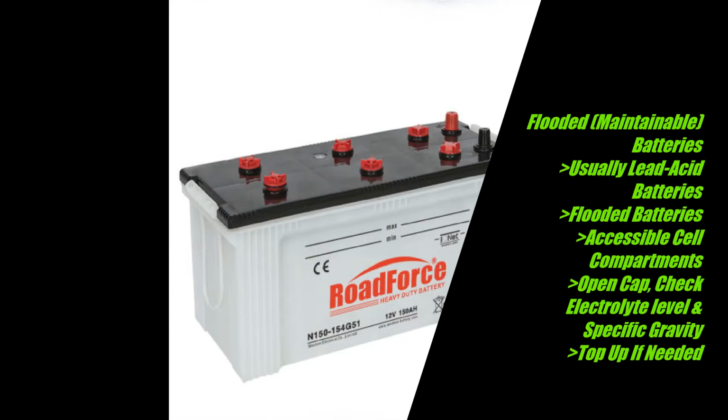So the first type is the flooded batteries. They are maintainable and are usually the lead acid batteries with individually accessible cell compartments. These compartments are filled with electrolytes and have caps on them for easy access. You can open the cap and check the electrolyte level in the compartment, and also use the hydrometer to check the specific gravity of the electrolyte. If you notice that the electrolyte level has dropped from the set level, then you can top up the cell so that the battery keeps performing well.